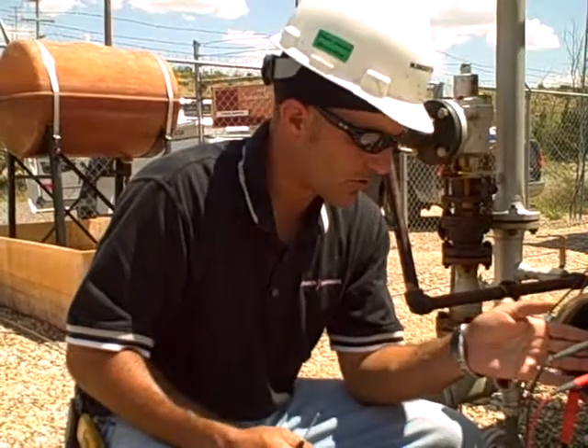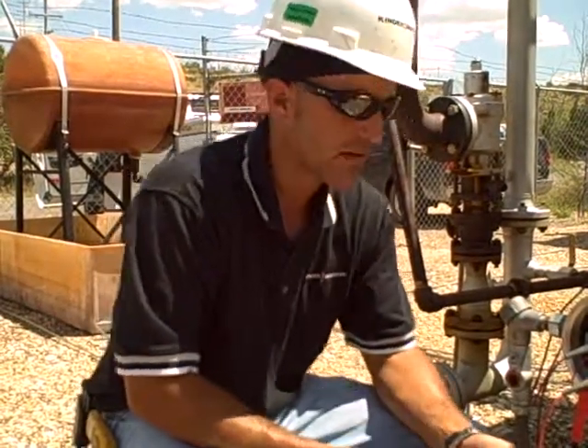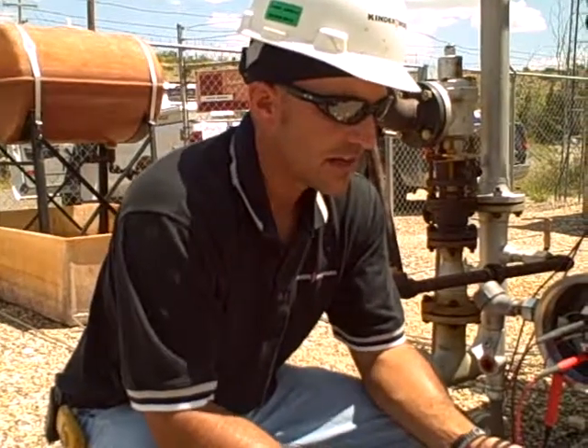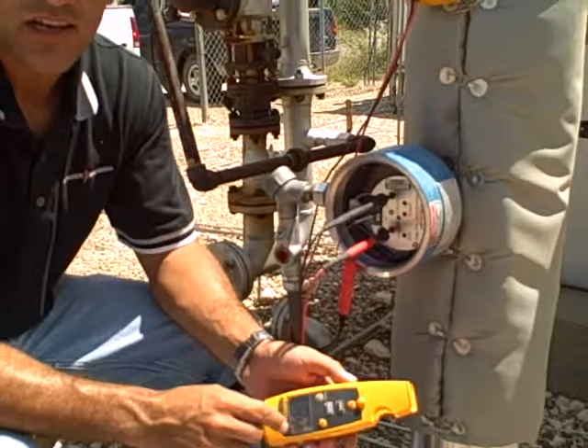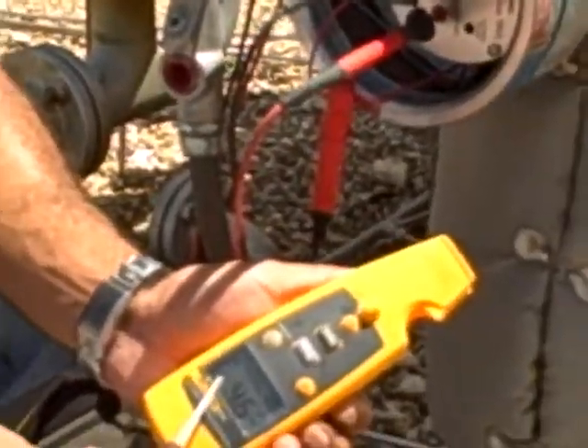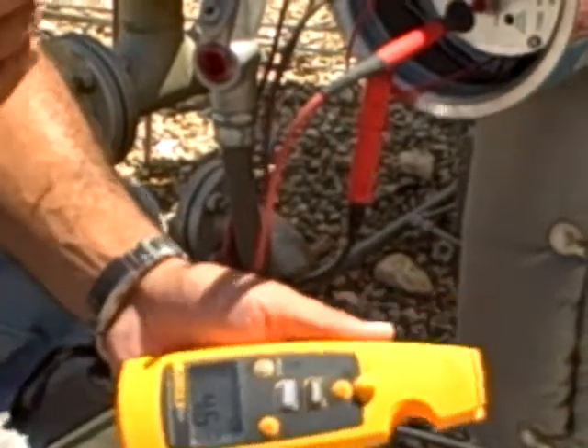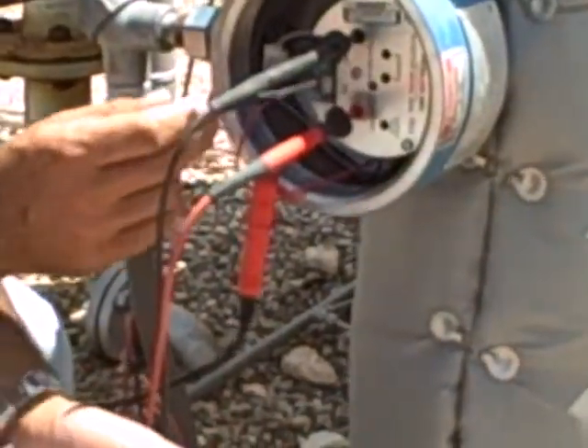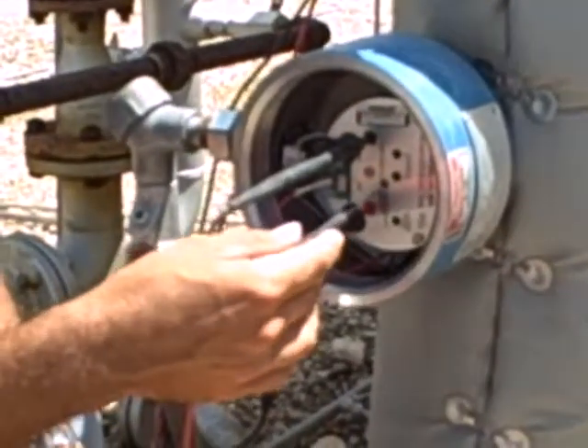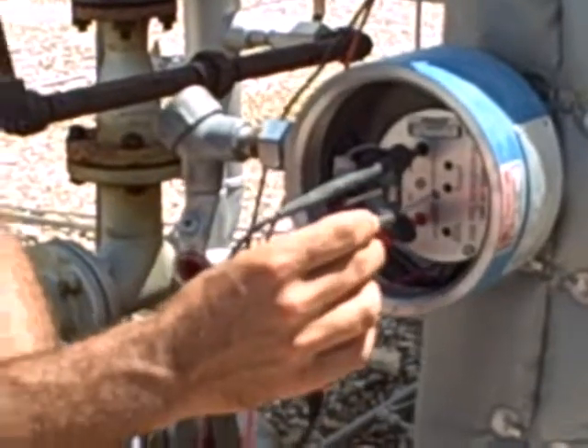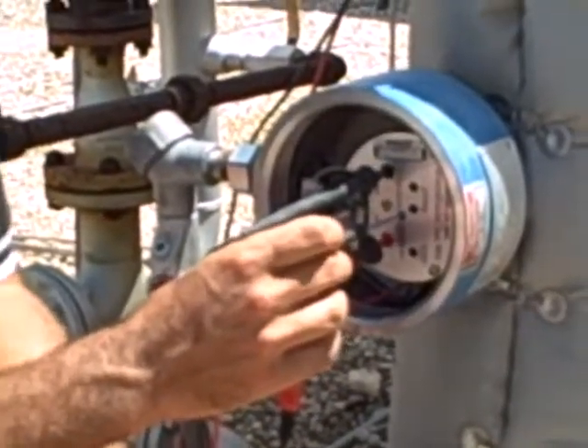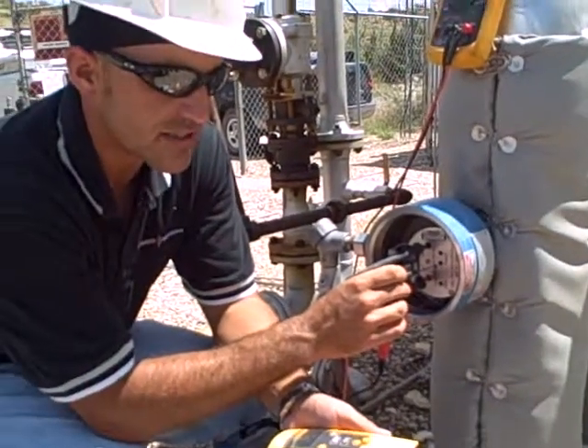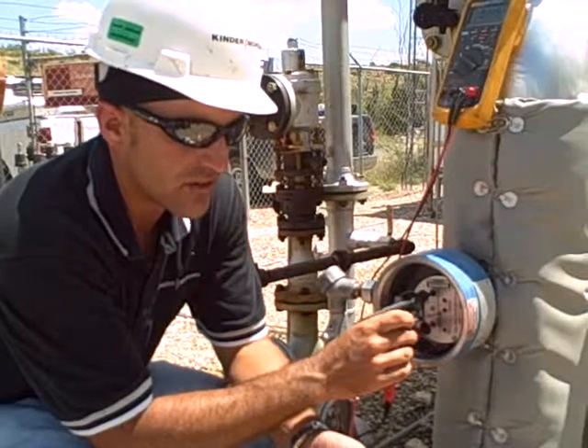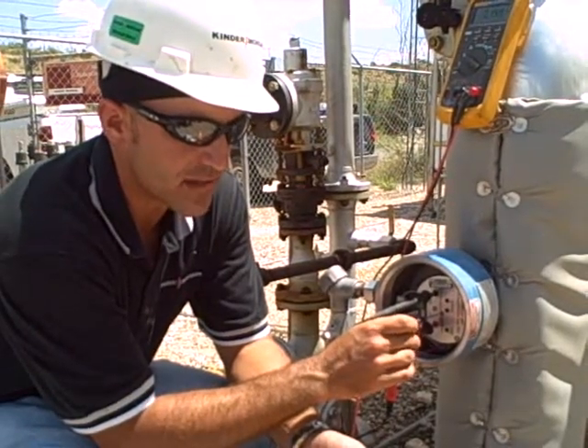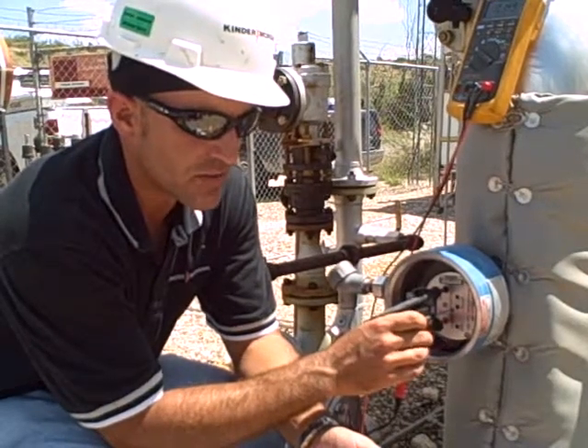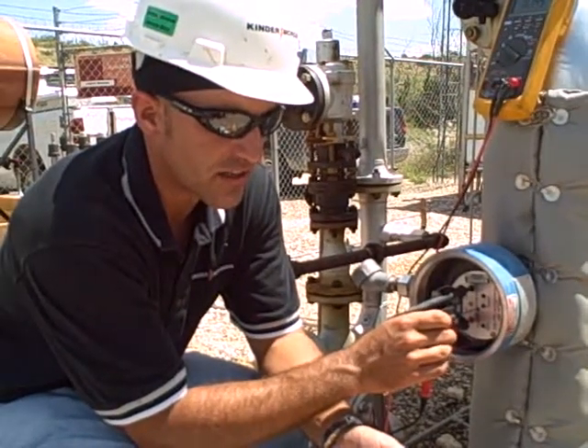Okay, now that I got my voltage set, I need to go ahead and get my 4 to 20 milliamp set. So on the 771, it actually has a percentage on there, so you don't have to do your mathematical calibrations. You can just look at the percentage. Now when you're adjusting the 4 to 20 milliamp on your probe side or your reference side to what you're calibrating it to, you need to use the 4 to 20 milliamp adjustment screw. Stick your screwdriver on there, and you gotta make real tiny adjustments. It's at 3.9% right now, so you need to make tiny turns with this. It's really sensitive, and it takes a second or two for the meter to actually read the milliamps. So you need to take your time while you're doing it.